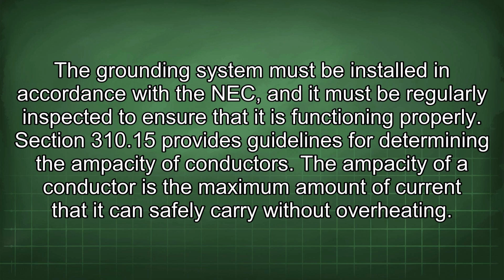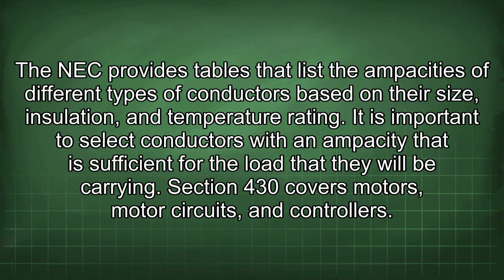Section 310.15 provides guidelines for determining the ampacity of conductors. The ampacity of a conductor is the maximum amount of current that it can safely carry without overheating. The NEC provides tables that list the ampacities of different types of conductors based on their size, insulation, and temperature rating. It is important to select conductors with an ampacity that is sufficient for the load that they will be carrying.